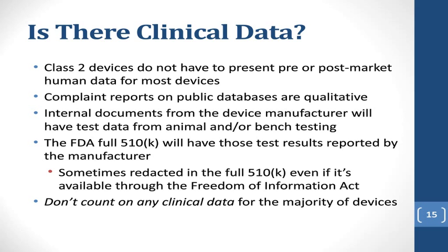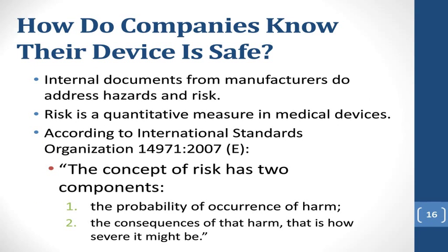And as I just said, if there's no clinical data, you're saying to yourself, well, how do these people get the product out on the market? Well, as I just talked about, there are really extensive internal documents for most devices, where groups of safety engineers, design engineers, anyone who's involved in the production of the device, get together and brainstorm and try to define what the risk is. There are also international standards that are used, and these guidance documents are very well known to anyone in the medical device design business.